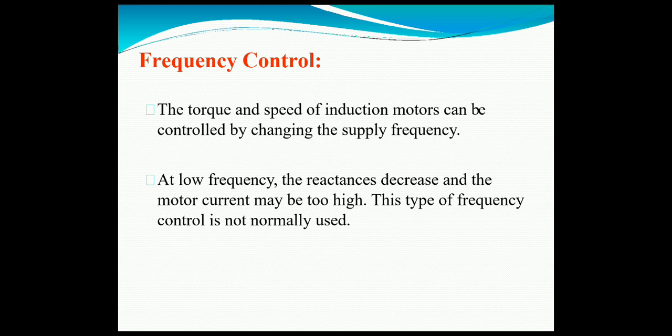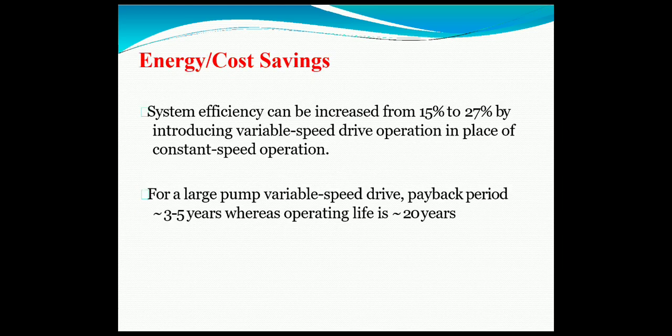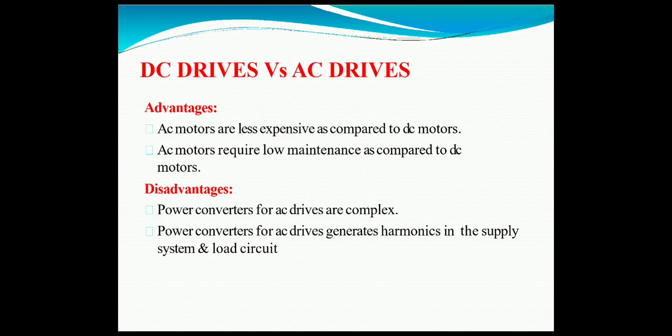If we are able to change the supply frequency, then we can control the speed and torque characteristics of the motor. At low frequency, the reactance decreases and the motor current may be high. This type of frequency control is generally used in industrial applications. System efficiency can be increased from 15 to 27 percent by incorporating a variable speed drive in place of constant speed operation.